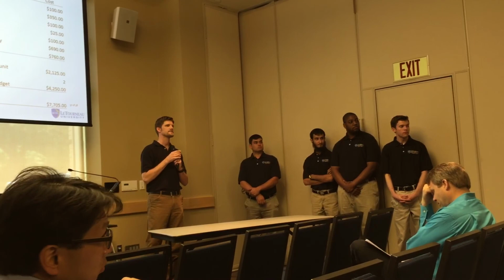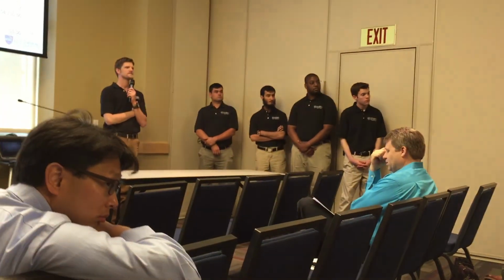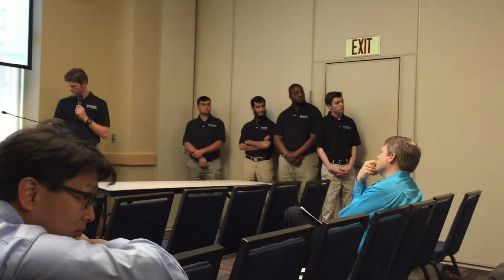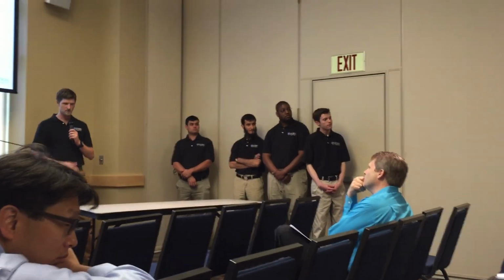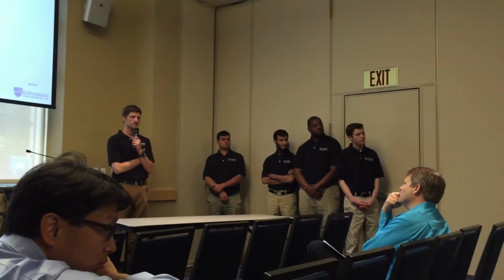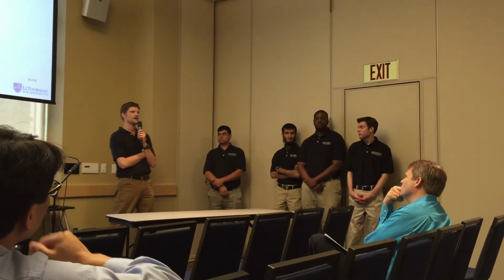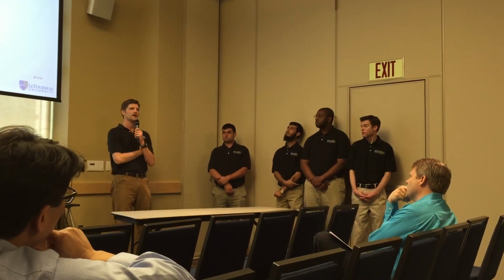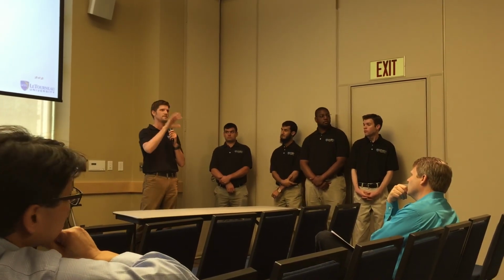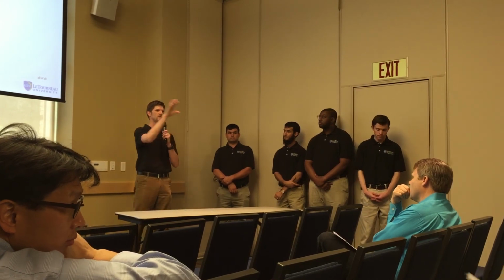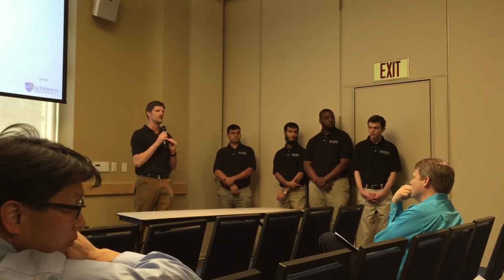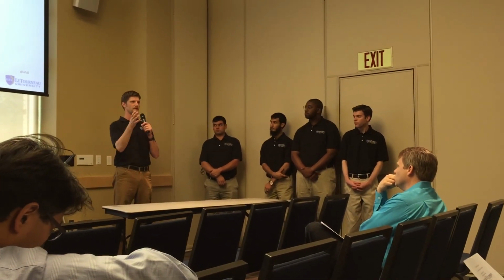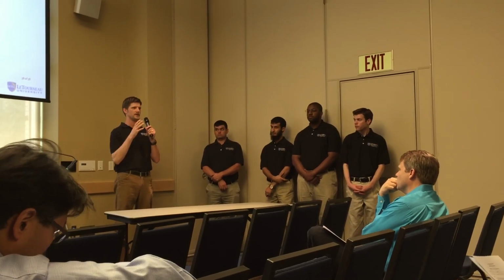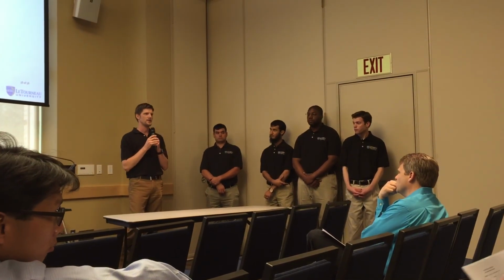I was wondering, when using this testing device, did you see if it had the same results as, say, the $50,000 machine? Yeah, we were comparing it - those are actual comparisons of the same motor between the PDMA unit and our unit. So yes, we were comparing it, trying to see how we could calibrate it to get it within the range of the PDMA.